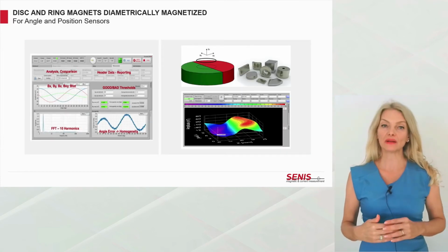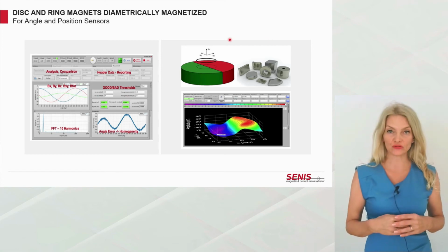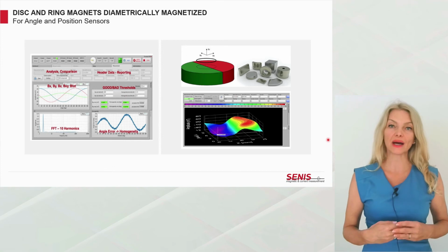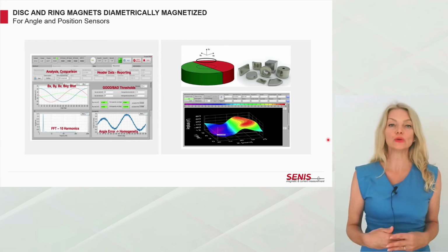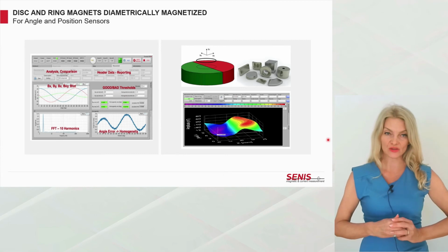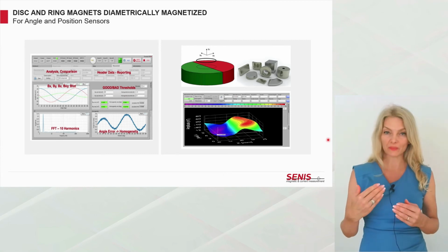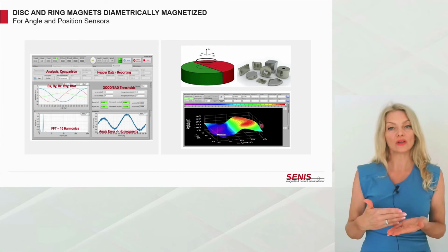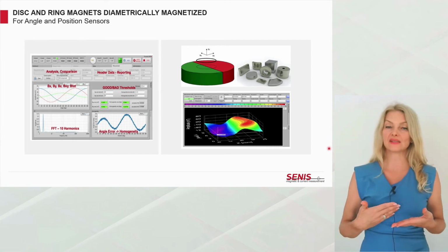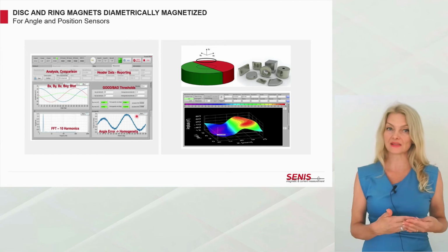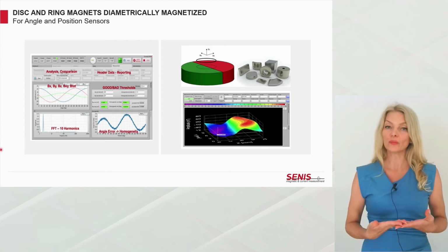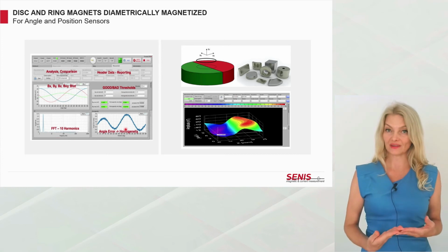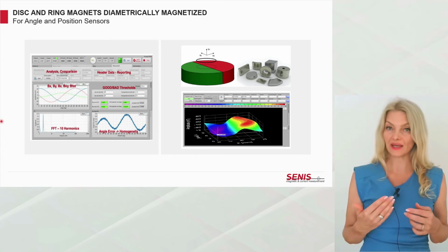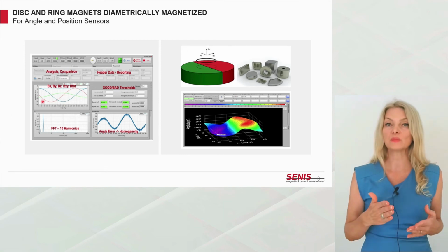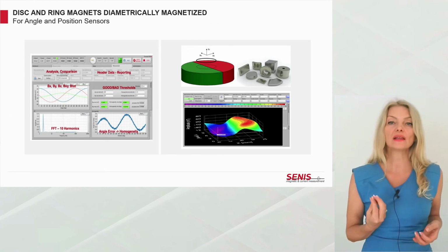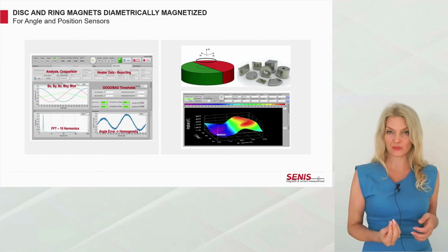As an example, here is the measurement of disc and ring magnets diametrically magnetized, which are usually used with angle and position sensors. Our 3D mapper maps around the magnet and visualizes the 3D graphs of the magnetization, providing analysis such as the angle error of magnetization and the inhomogeneity. It visualizes the magnetic flux density Bx, By, and Bz, measured in one single spot.